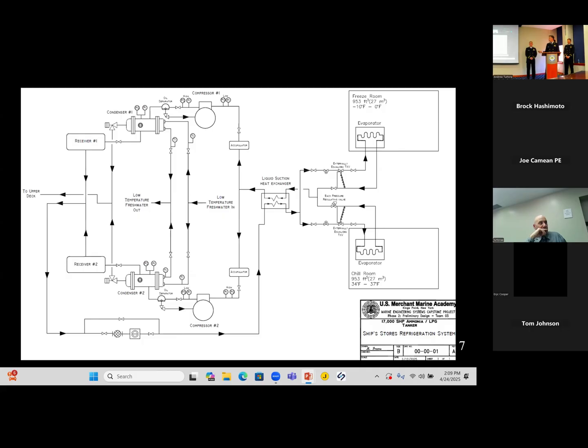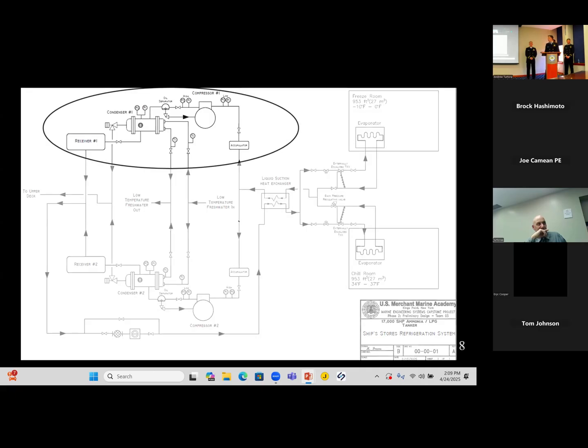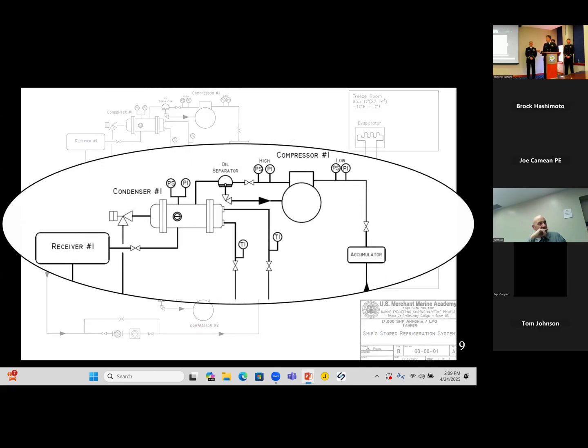As you can see, we have 2 compressor condenser units, a liquid suction heat exchanger, our externally equalized TXV valves with a back pressure regulating valve on each chill box, and then our 2 evaporators for both of our refrigerated spaces. First, we're going to look at our one compressor condenser unit. This is comprised of an accumulator, which is used to accumulate moisture of the refrigerant prior to entering the compressor to prevent slugging within the compressor.